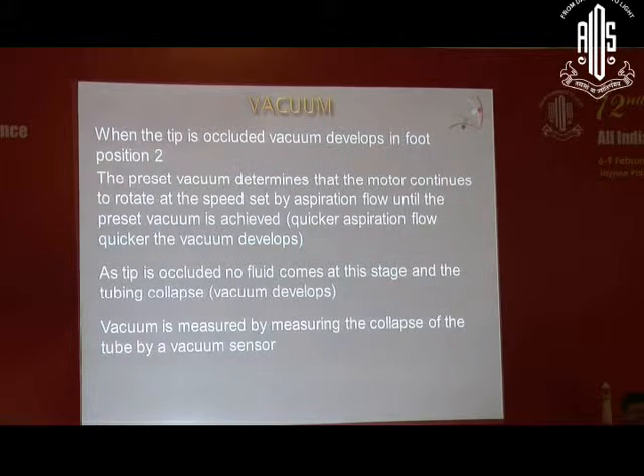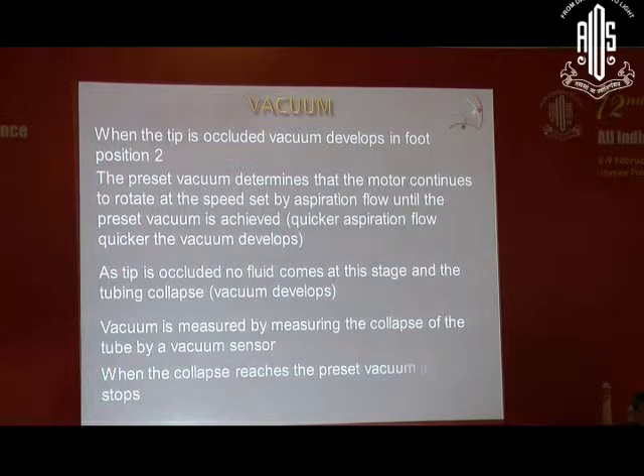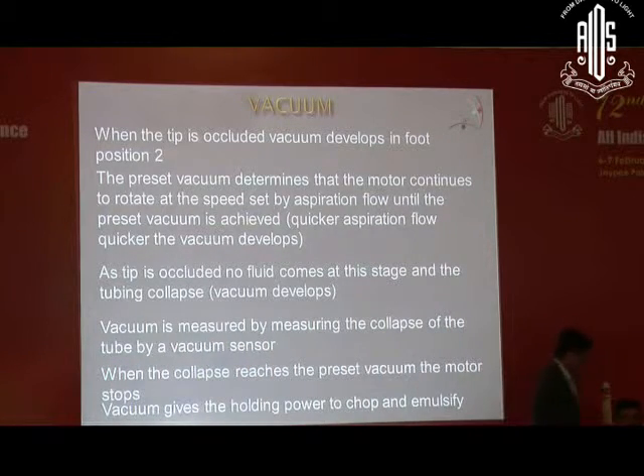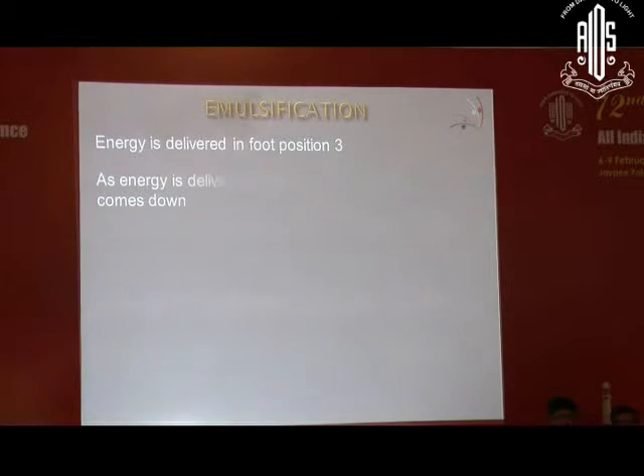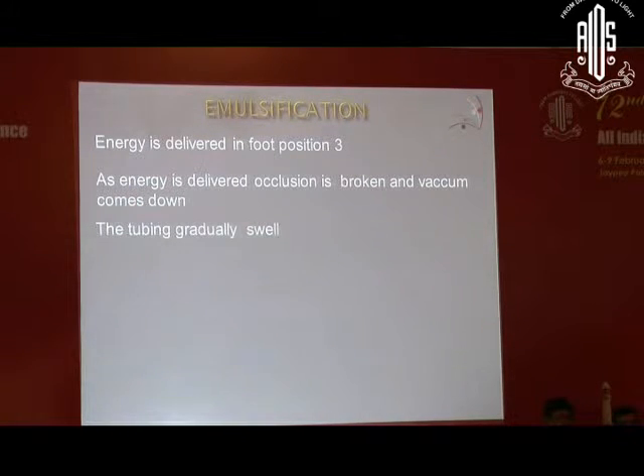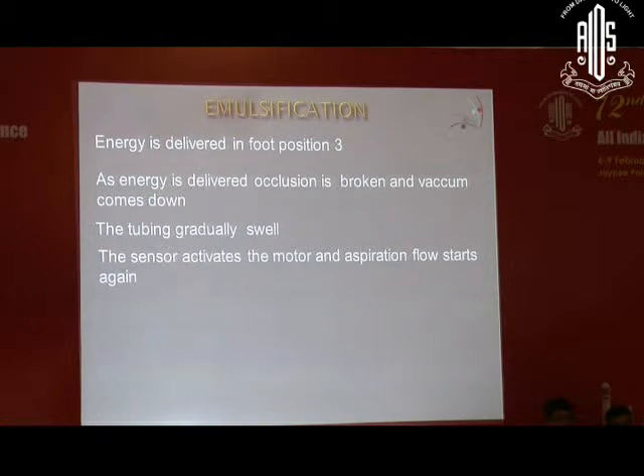The vacuum is measured by measuring the collapse of this tube by a vacuum sensor. And when the collapse reaches the preset vacuum, that is say 200 or 300, the motor stops, thereby the aspiration flow stops. The vacuum again builds up, and the vacuum gives the holding power to chop and emulsify. So energy is delivered in foot position 3. As the energy is delivered, the occlusion is broken and the vacuum comes down. The tubings gradually swell, and the sensor activates the motor and the aspiration flow starts all over again.